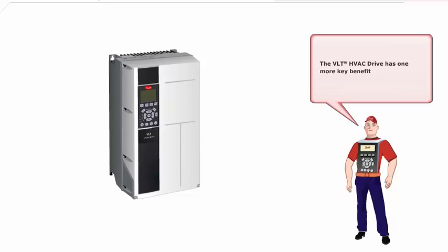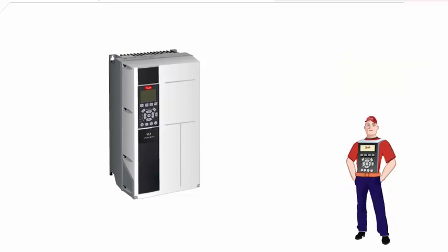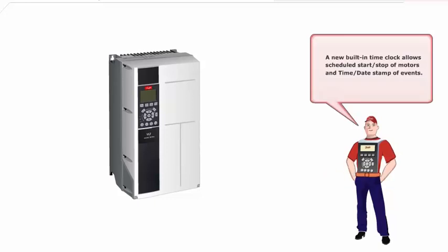The VLT HVAC drive has one more key benefit. A new built-in time clock allows scheduled start-stop of motors and time date stamp of events. This provides time scheduling of the fan when a building management system, or time clock does not exist.